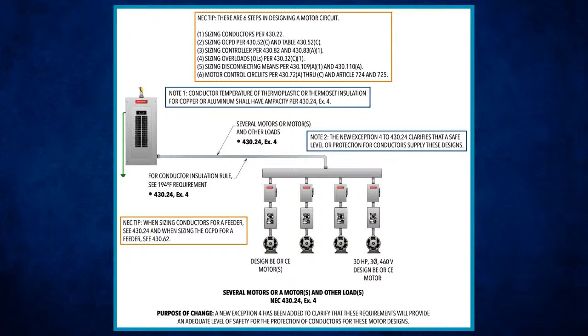I'm not going to spend much time on this since Jeremy took up a lot, but look at 430.24, where you have several motors and other loads. They look at exception 4, same thing we're doing on everything else, but here they mention a group of one or more motors rated as design B or CE motors.